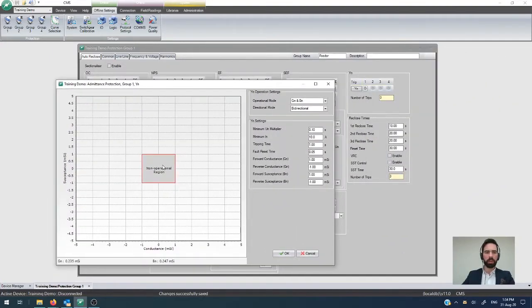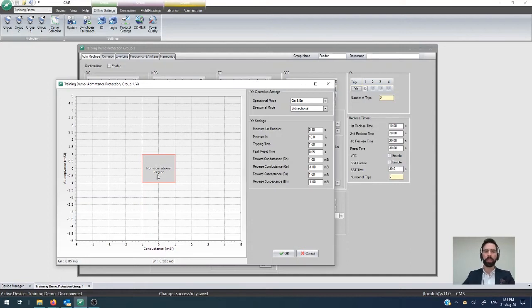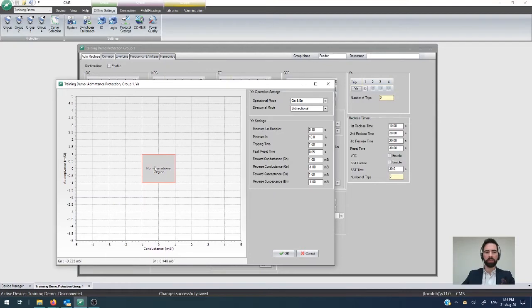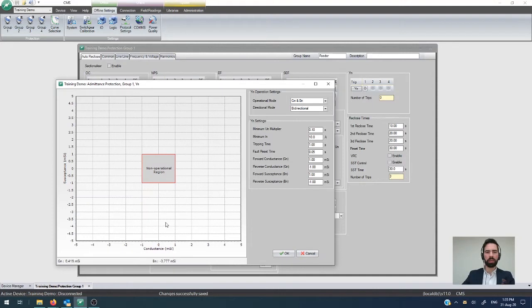We click YN and we can see that during a normal operation you shouldn't have any leakage through a fault or very little and hence you stay within the non-operational region. This is an inherently directional element so anything on this side is going to be in the forward resistive direction or on this side it's then negative conductance so it's negative resistive direction. And likewise then, susceptance is both in the capacitive and inductive directions in this plane along here.